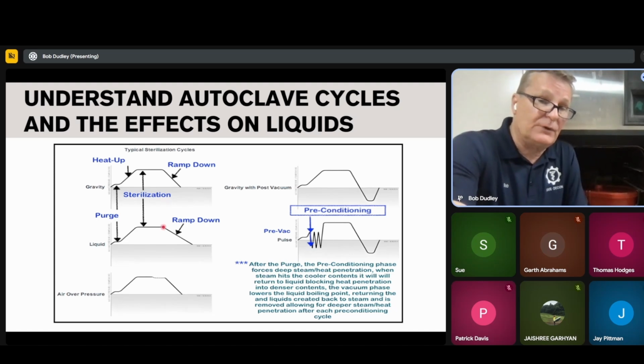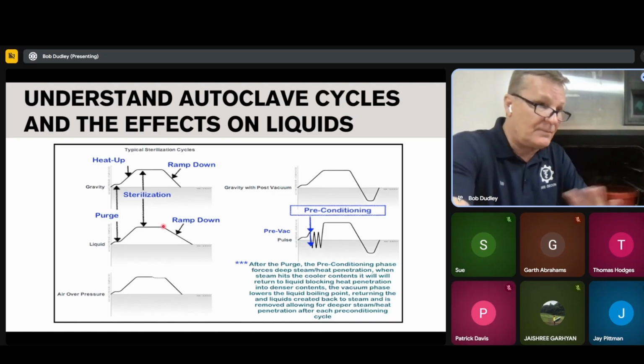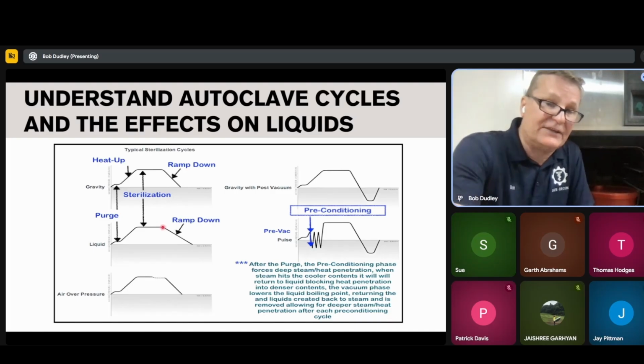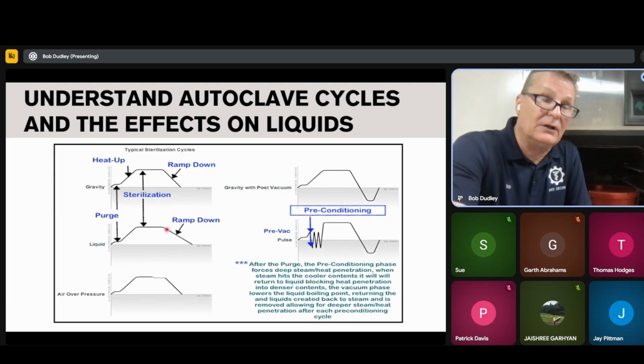And what it's doing is it's resting, and it's trying to take away some of that heat that's in there. What generally happens on this ramp down is you should have what they call a slow bleed valve. It opens up and it just creeps it down. Now, the goal is to lose 1/2 psi for every 2 to 3 minutes.